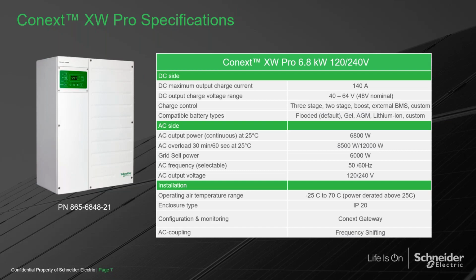This is a standard spec sheet of the XW Pro inverter. I won't touch on this too much, but just to point out a couple things: this is a 6.8 kilowatt inverter at 25 degrees Celsius. However, it's a really robust product for starting big motor loads, so we can actually surge for 60 seconds up to 12 kilowatts. If you're starting an air conditioner or an inductive motor, the product is going to work, it's not going to fail when that application happens. In addition, we run 8.5 kilowatts for 30 minutes.